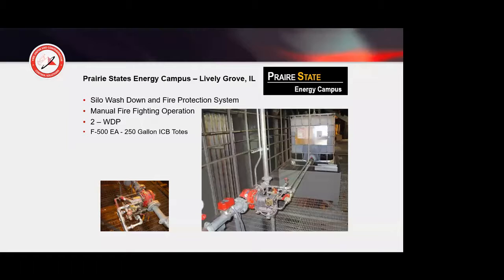Whereas with the water-driven proportioner, when you stop the water, it stops flowing through the water motor, so the piston stops, so agent flow stops. So this is just one of the projects here. You can see down here the water is going to flow. I can't tell from here which direction, but one direction or the other. I believe water's coming in from this direction, going through the water-driven proportioner, and then it's going up to whatever the hazard is it's protecting.